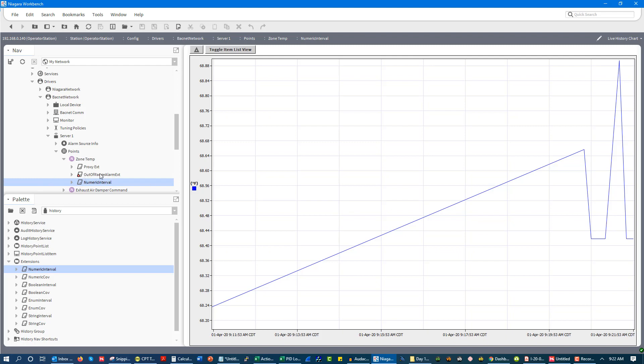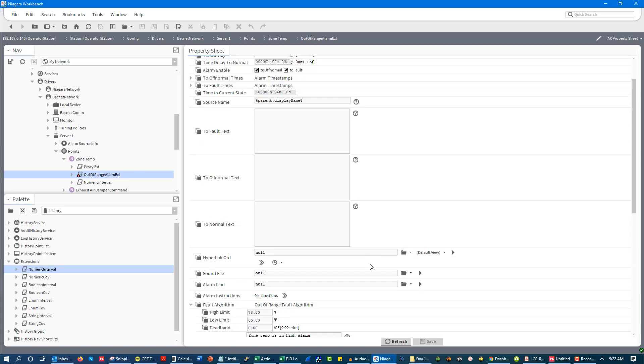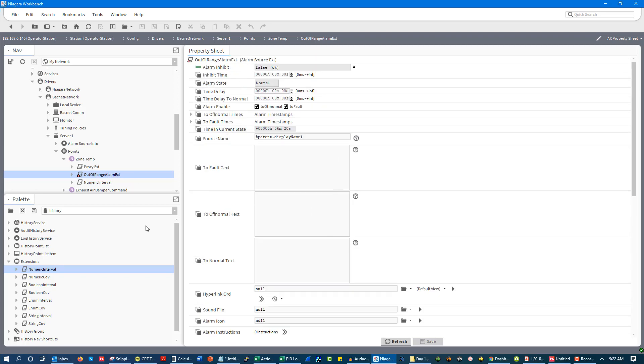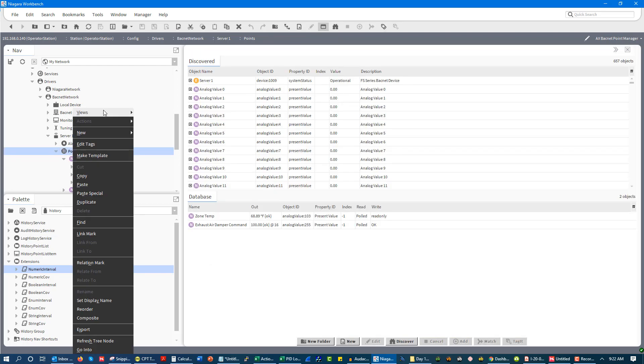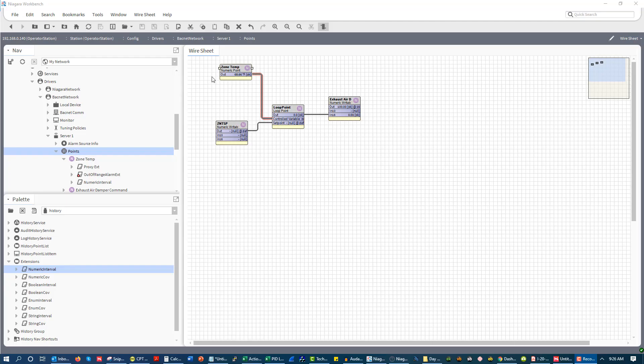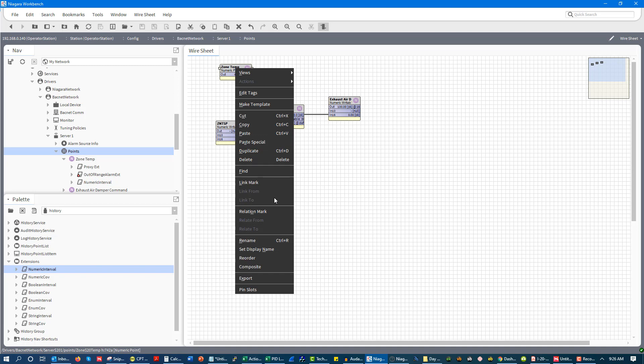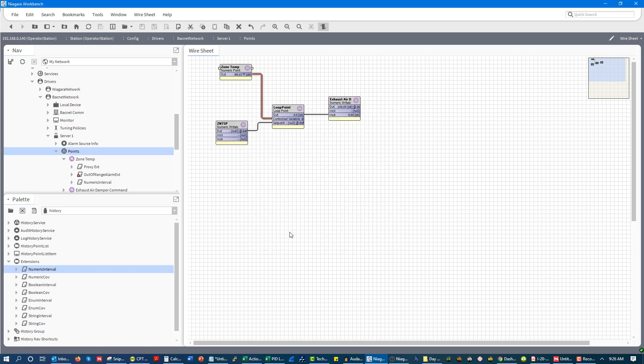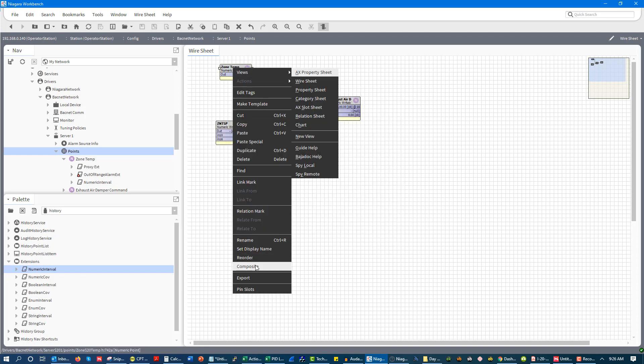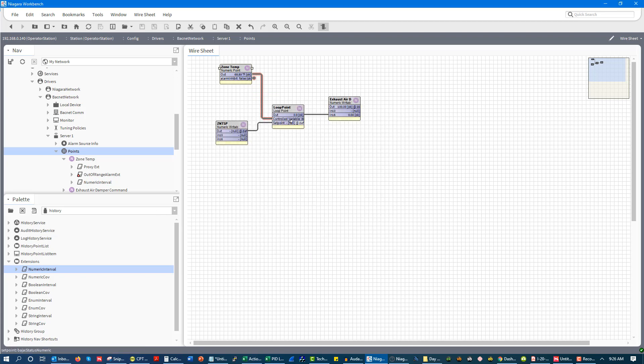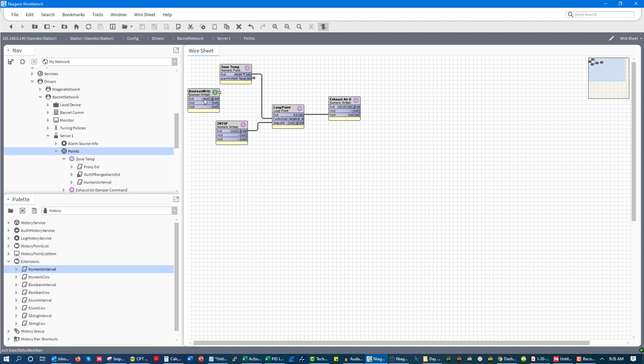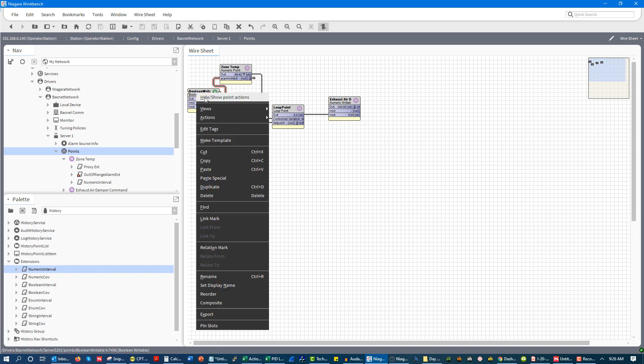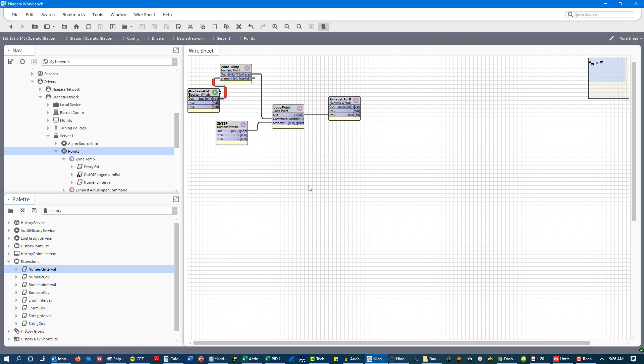And with alarms, it's just about getting your threshold right. The really big thing with alarms is tying it to occupancy. So if we go and I go to points and I go to views, I go to wire sheet, and I'm going to add the point for the point extension, that way I can go and enable the alarm or disable the alarm. I've got my alarm inhibit. So then I would add a boolean writable and my alarm inhibit would write to that boolean writable. And I could set this to true and that would inhibit the alarm that would keep the alarm from triggering. So that is how I could disable the alarm when I don't have the space occupied.